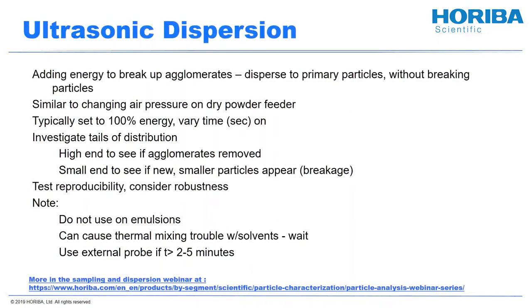A question came in: if you have low accuracy or low reproducibility, what might be the issue? Generally, if you have a reproducibility issue, I would start by going back and looking at repeatability — those first tests of pumping and stirring. Once I know I'm repeatable with the same sample in the analyzer, I would move on to looking at ultrasound, then choice of dispersion, and finally sampling — making sure you draw a representative sample from your container.